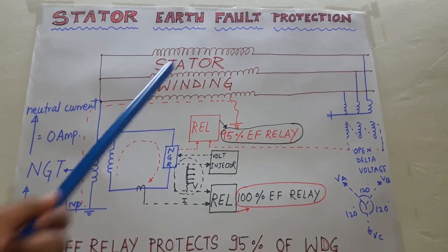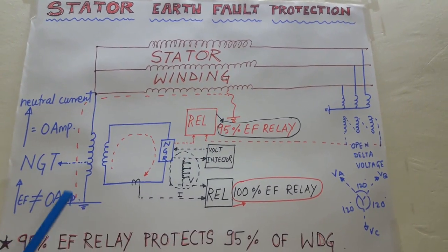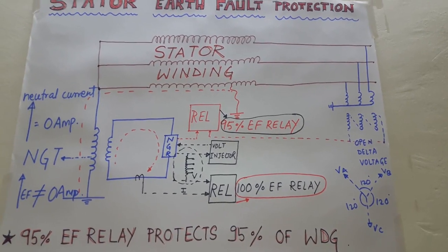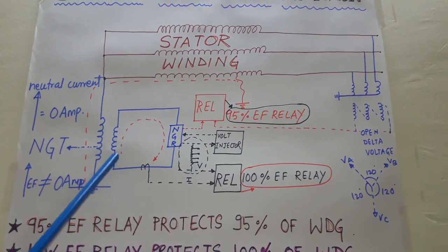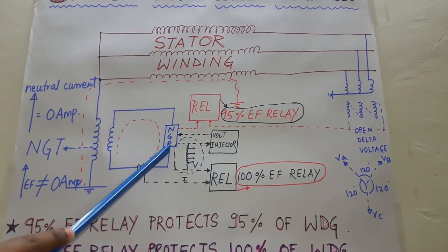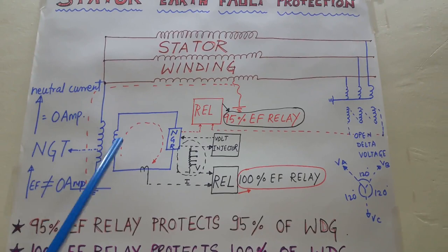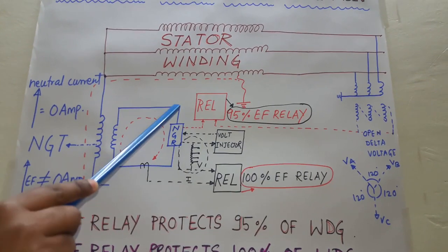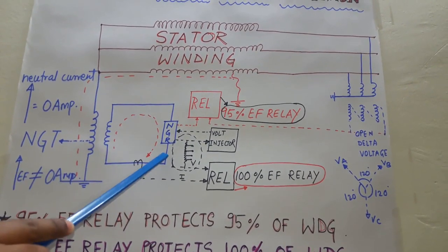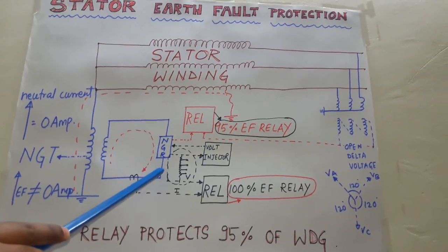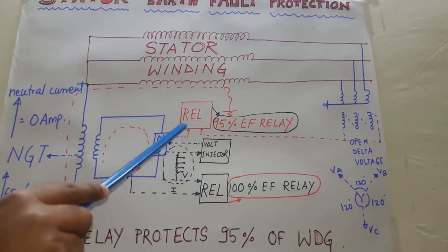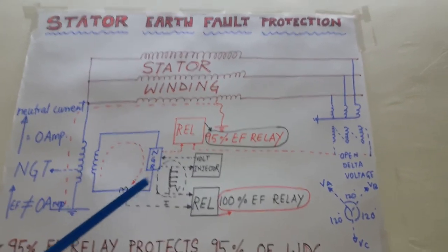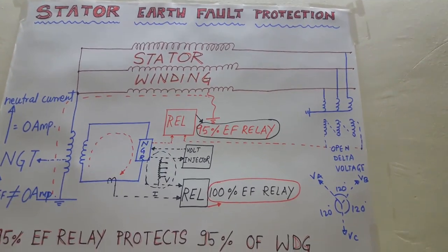Whenever any part of the stator winding is getting earthed, a current is seen in the neutral path — a current is flowing. This transformer is connected to the NGR, so when current flows through the primary winding, a current is seen in the secondary winding. Due to this current and the resistor present, a voltage drop is created across the resistor. This voltage drop is fed into the earth fault relay. In the earth fault relay there is a setting of voltage — if the voltage drop exceeds that setting, the relay will operate on earth fault.